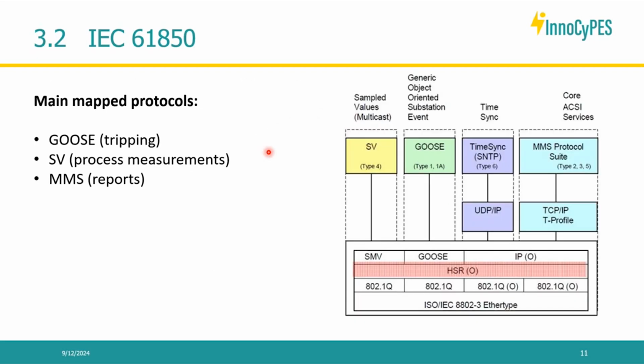Here we see the main protocols mapped into the 61850 services, which are the ones we'll be using today for the rest of the setup. First we have sample values, which is responsible for getting digitized voltages and currents from the VTs and CTs. It digitizes them and publishes them onto the process bus network. It's a multicast protocol with strict real-time requirements that should be very quick.